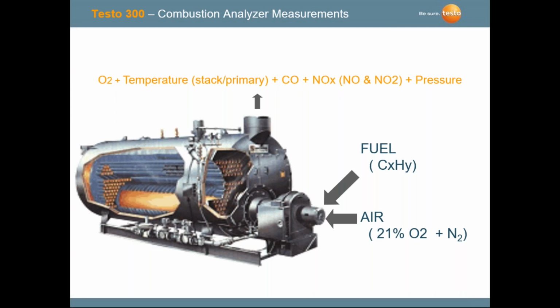When we talk about total NOx, and if anyone on this presentation is doing EPA evaluations, compliance level testing, it may require you to have both sensors, NO and NO2. And when you have two sensors like NO and NO2 for total NOx, this is going to move you up a level on a combustion analyzer, and it gets you into a model we call our Testo 350. So we do have you covered as well if you're doing total NOx.